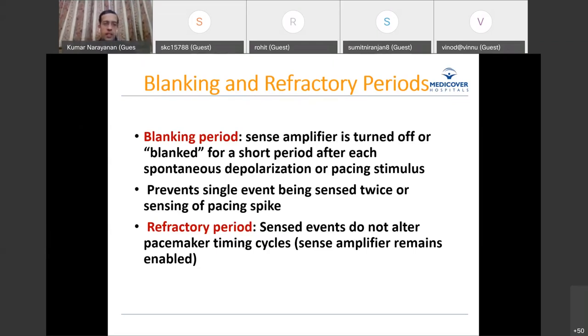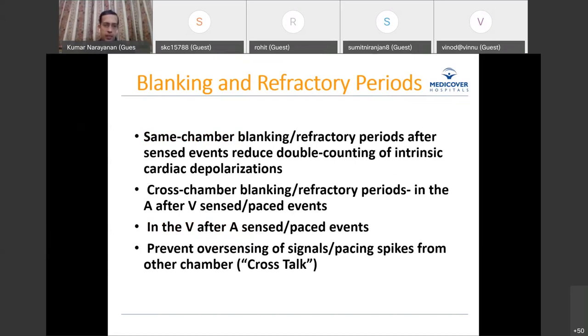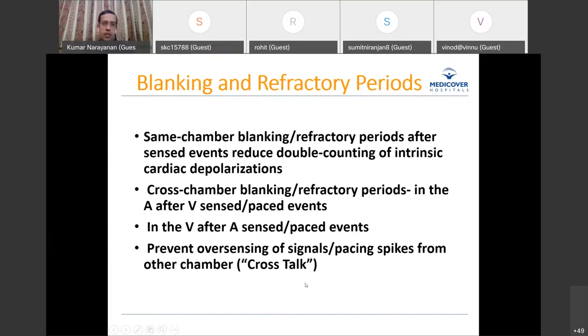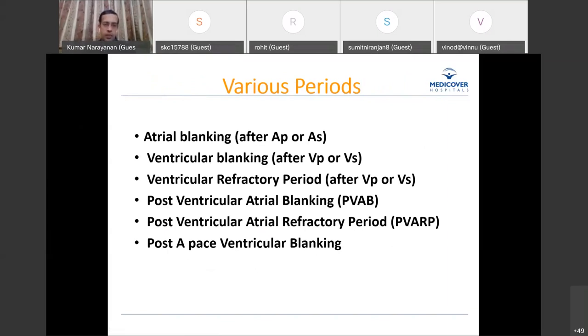In multi-chamber pacing, you also have cross-chamber blanking and refractory periods — a refractory period in the atrium after a V-sensed or V-paced event, and a refractory period in the ventricle after an A-sensed or A-paced event. These prevent over-sensing of signals from the other chamber. Various types of blanking and refractory periods will be covered in more detail in the session on dual pacing timing cycles.